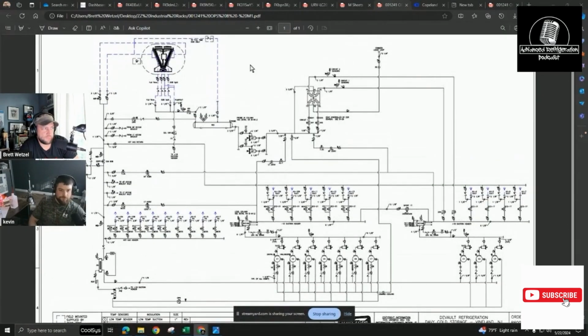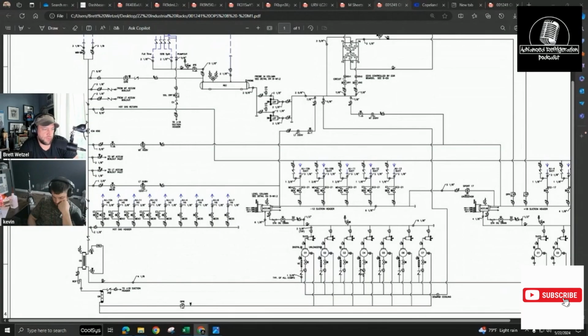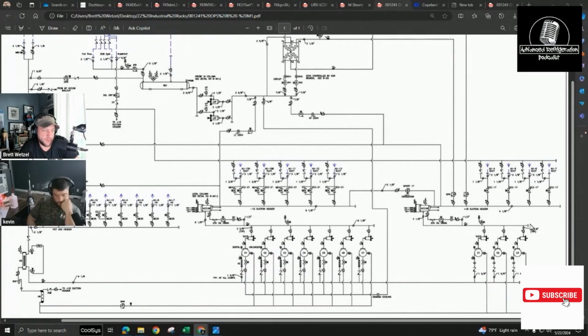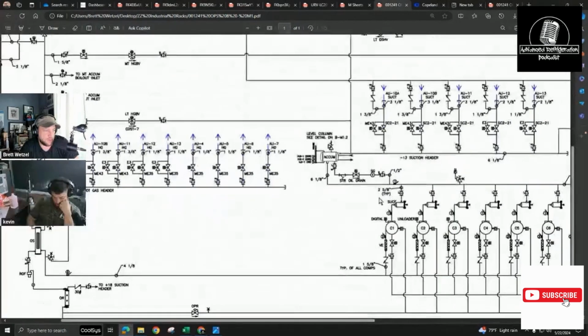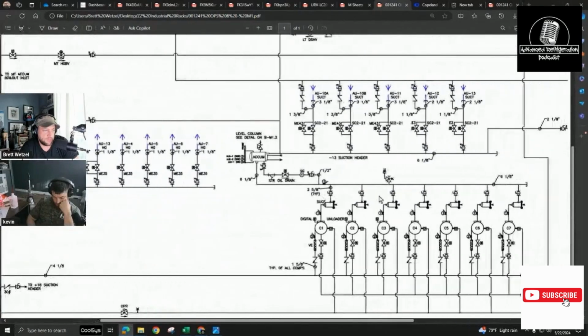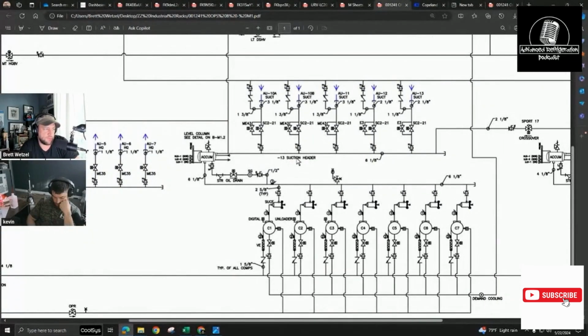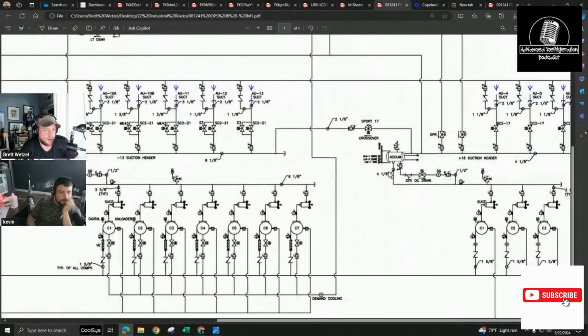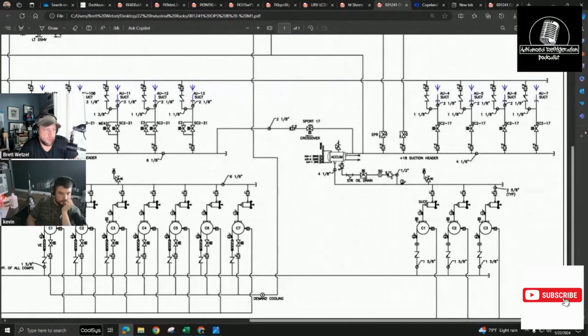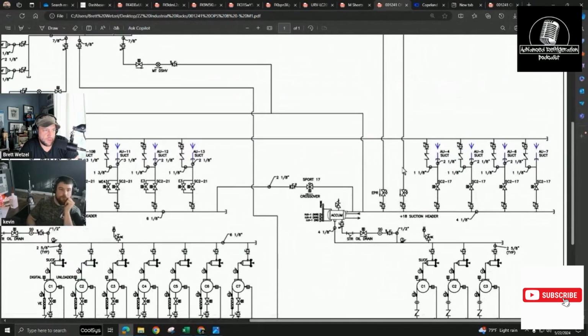Let's zoom her in a little bit. So I believe this is our medium temp side. Yeah, no, my bad. Medium temp side over here, the low temp side over here. The reason I was able to see that is by looking at the diagram, zooming in: you've got 18 degree suction and minus 13 degree suction. The other thing was, why would you have hot gas on your medium temp? This is a hot gas rack. It might be doing hot gas on that one too. I'm not sure. We've got to look further into it.